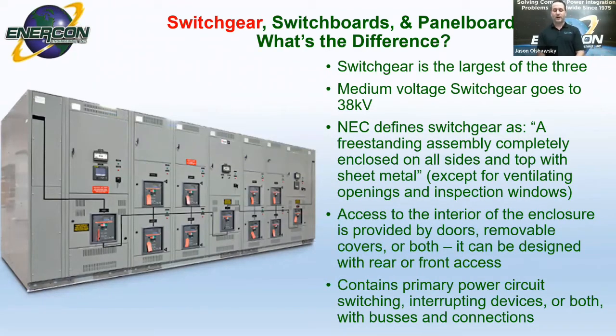So switchgear is the largest of the three, as it contains the highest amount of current draw back to the utility source. Medium voltage switchgear tops out at 38 kV and is usually a larger footprint than low voltage. NEC defines switchgear as an assembly completely enclosed on all sides, top and bottom, with sheet metal except for when ventilation openings and inspection windows are utilized for that gear.